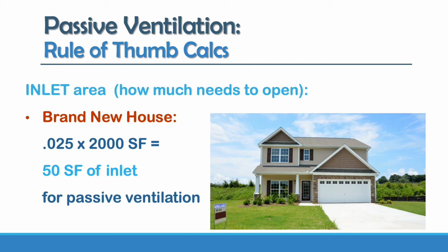And if you remember, we can get better airflow when we have a smaller inlet area than the exhaust. So if I have a 2.5 square foot open window in that 100 square foot room, I would have another window open that is larger than 2.5 feet in order to encourage that airflow. And it should be on an opposite wall, or at least perpendicular, if not through an open door and a second story window open.